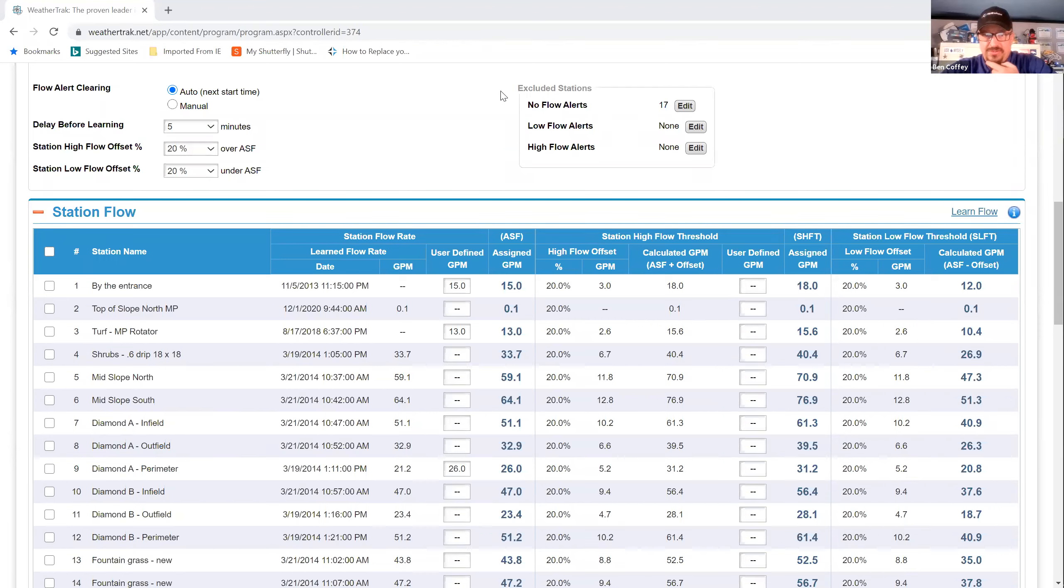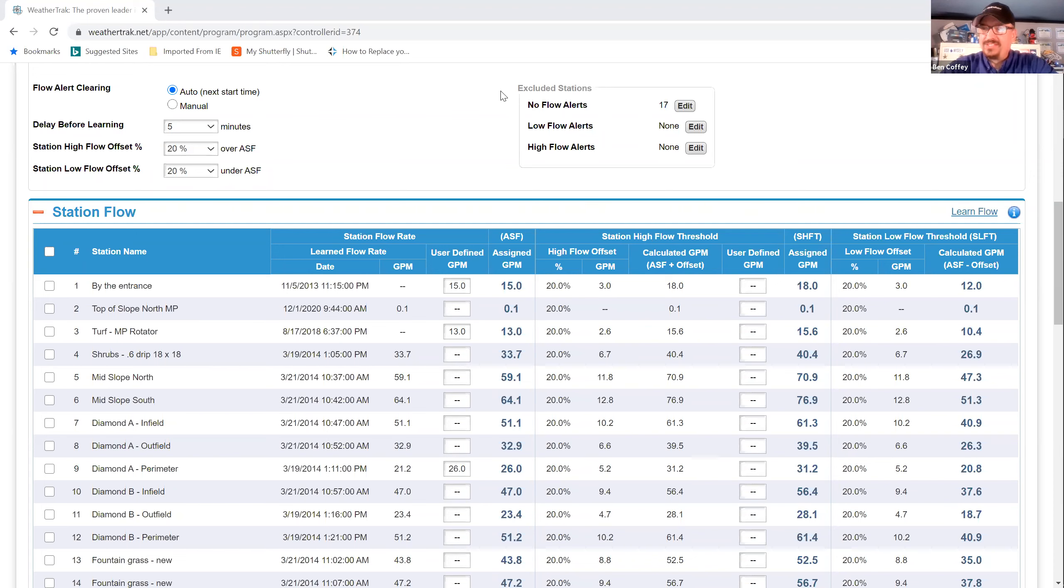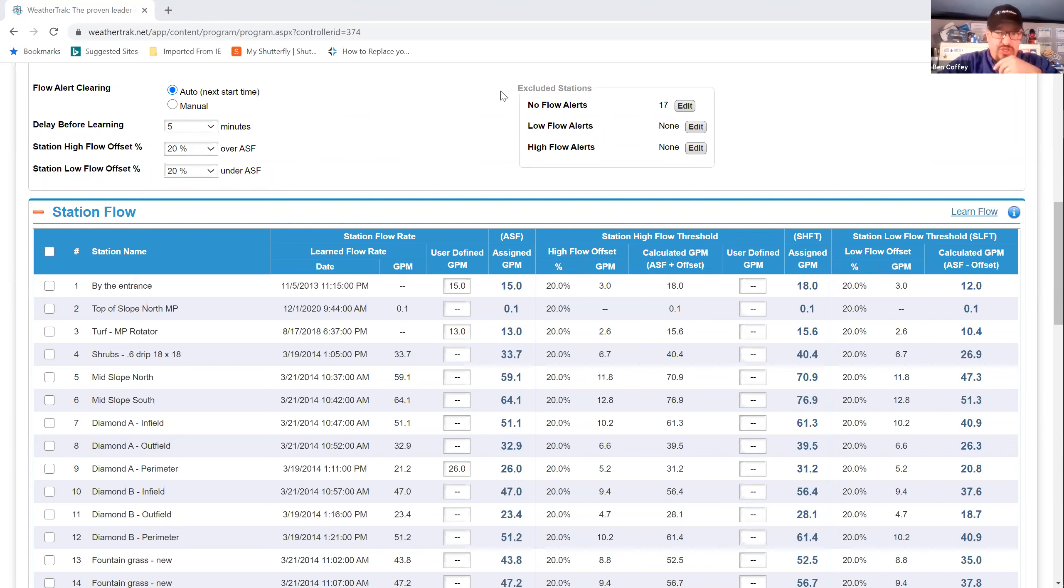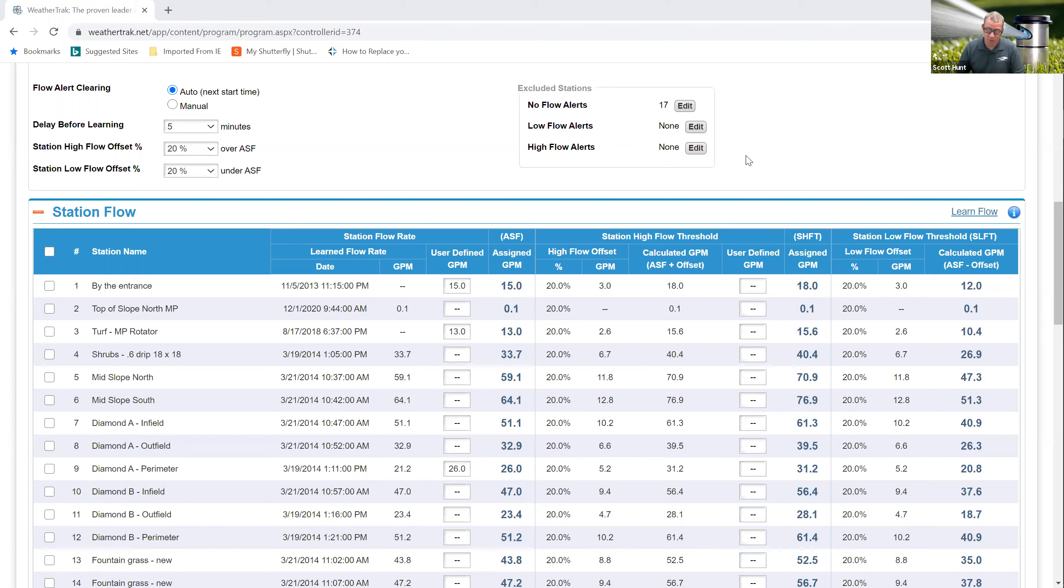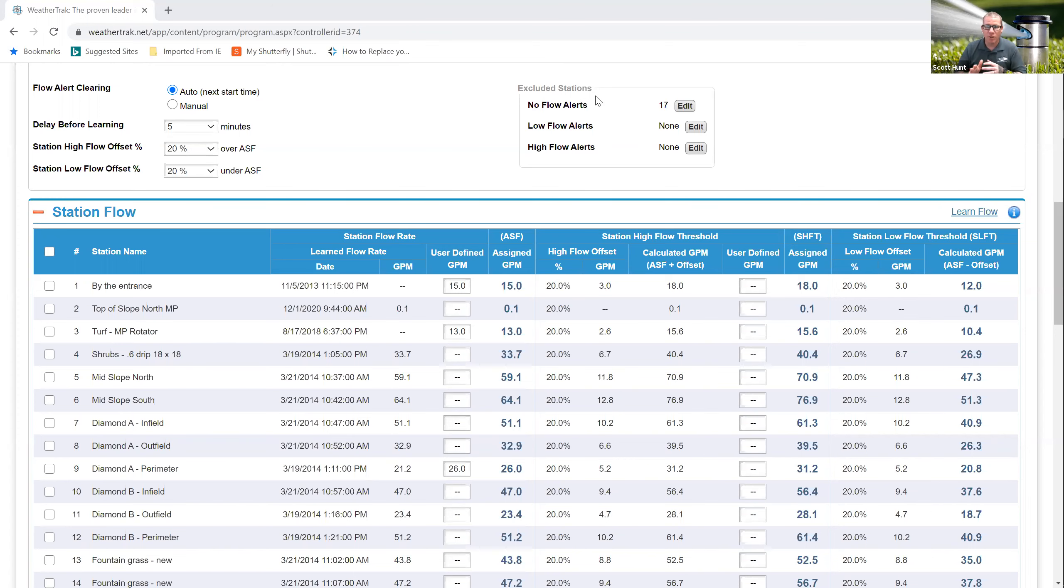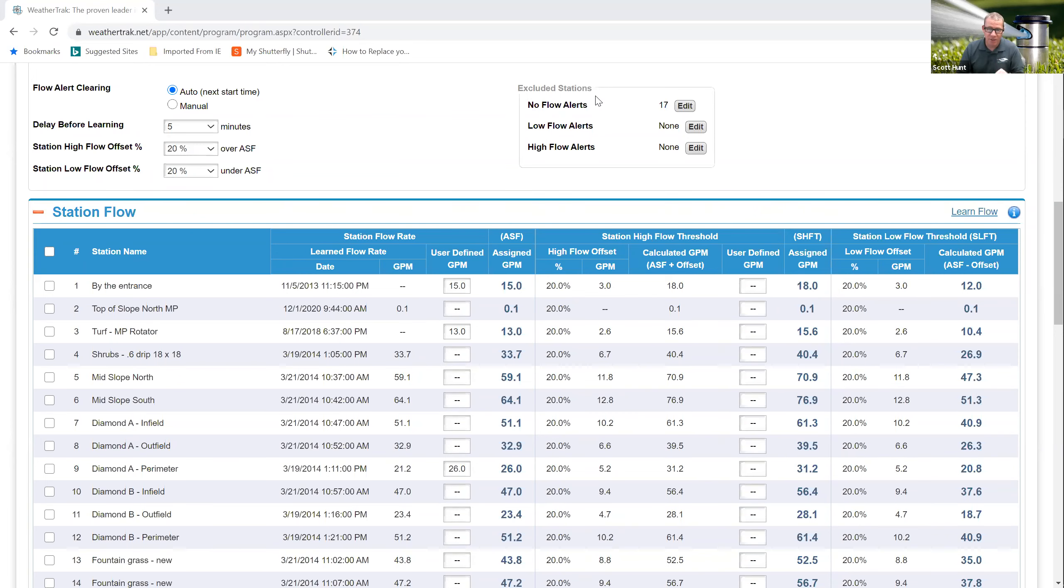So we have some questions. Where do you start on the high flow, low flow percentage? I think we've covered that. Scott just said he uses the defaults. Should you relearn flow at any time? That's a personal management question that I would love to hear Scott answer. We relearn flow typically anytime there's an expansion on the system or a large repair. If we're doing a retrofit on a station where we may be changing the flow or anything like that. And sometimes I'll do it at the beginning of a season, just to make sure after I've done my full system check and we've got the system all fired up, everything's good to go. I may go ahead and relearn flow just to compare what it was running at last year and make sure that it's good to go for this season.